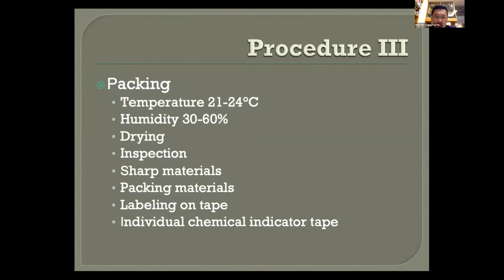And the next procedure is to pack. The packing space has to be kept with appropriate temperature and humidity. We recommend the temperature to be between 21 to 24 degrees Celsius, and the humidity has to be between 30 to 60%. And before packing, the medical items have to be dried, and we have to check whether all the items have been dried before we pack them.